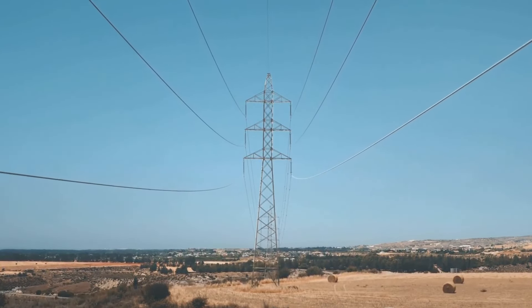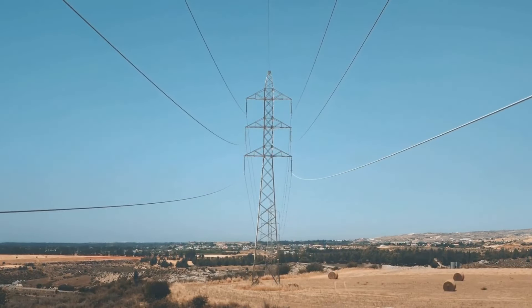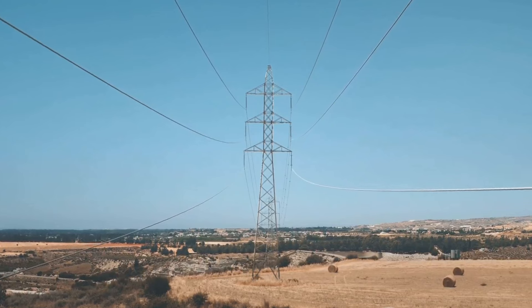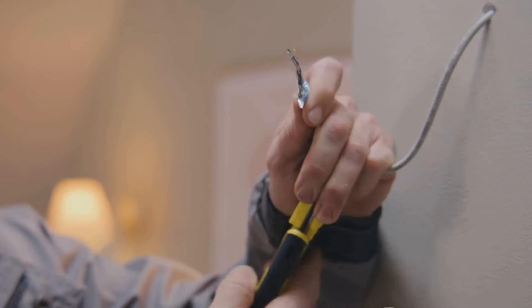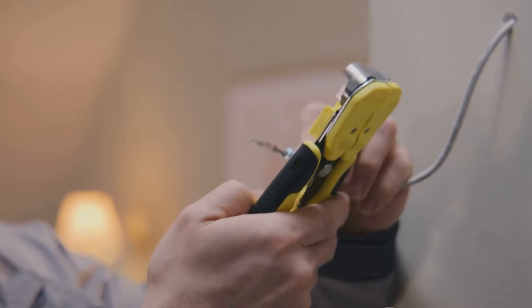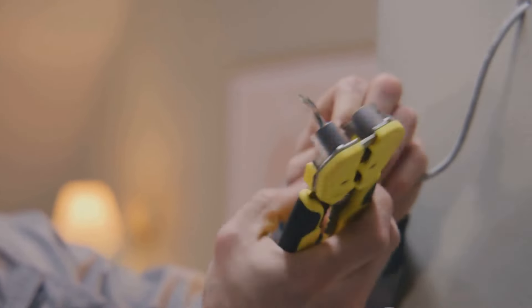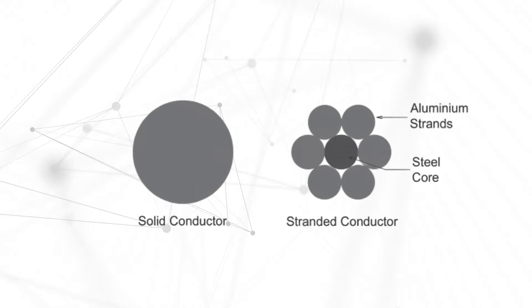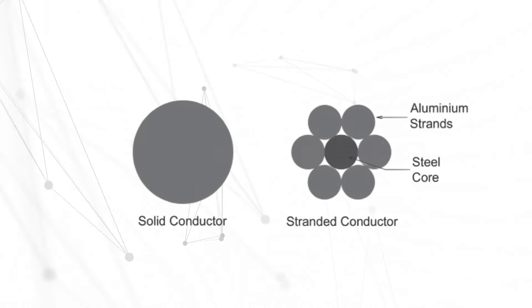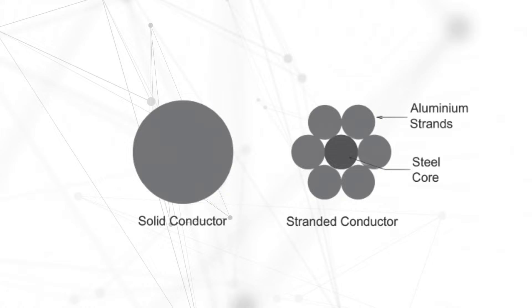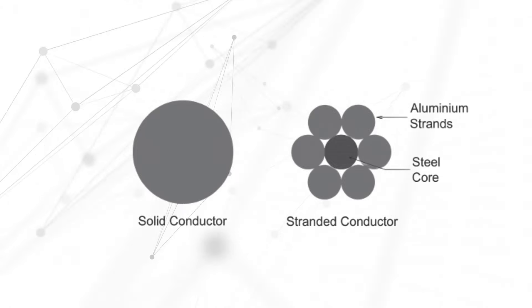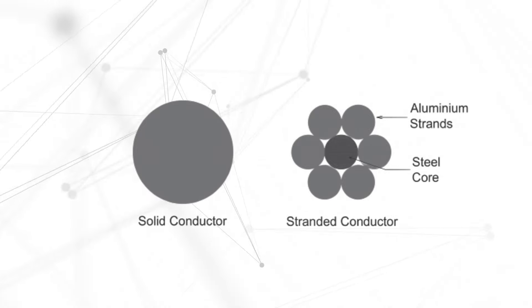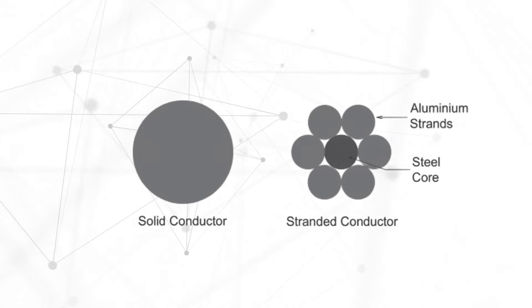Stranded conductors are popular in electrical power systems for transmission and distribution lines. A stranded conductor consists of several thin wires of small cross-sectional area, known as strands. At the center of a stranded conductor, we find a steel conductor which provides high tensile strength. The outer layers are made from aluminum conductors, which provide conductivity.